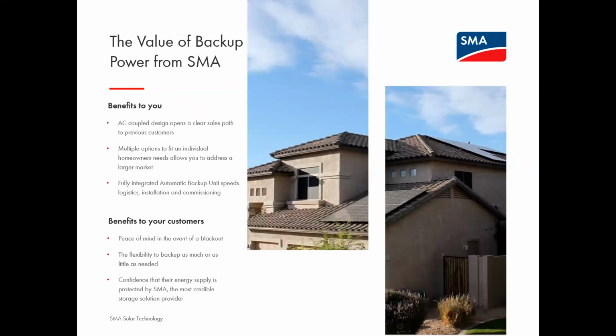So the value of this backup power use case that we provide from SMA, the AC coupled system design, really makes it a clear, easy path for you to go back to your existing customer base and upgrade their PV plants. That's just the inherent nature of an AC coupled system design. We do offer quite a number of options to allow you to integrate the energy storage into the home, both whole home backup possibilities as well as backing up protected load panels. And the fully integrated automatic backup unit really does speed up the whole design, commissioning, installation, and so forth.